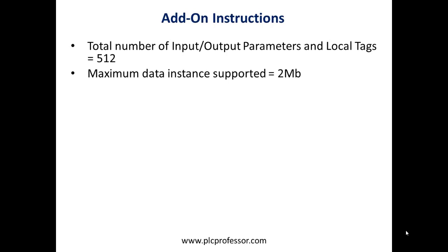The maximum data instance supported is 2 megabytes, which is actually quite a bit. Add-on instructions are edited offline only — you cannot edit an add-on instruction while the program is running, not even in program mode. You have to save, go offline, make your edits, save, and then download.